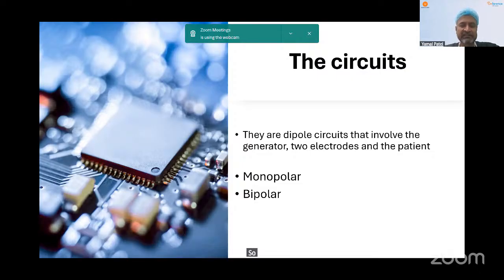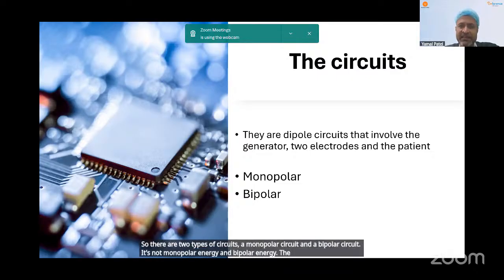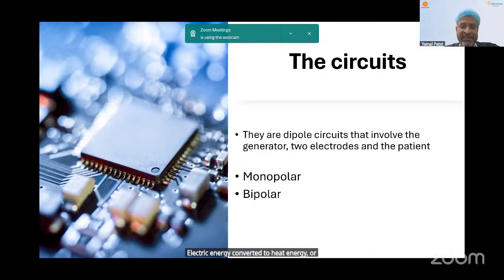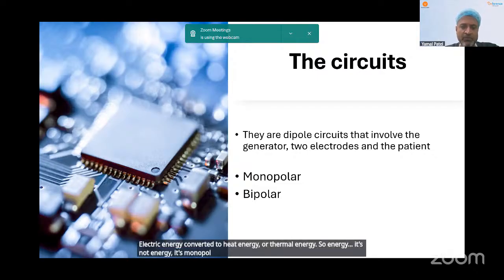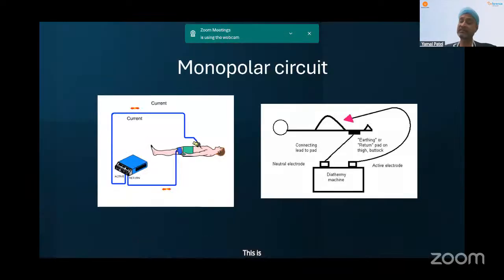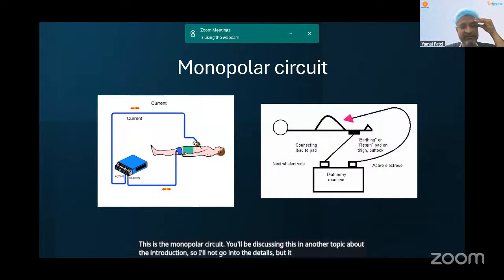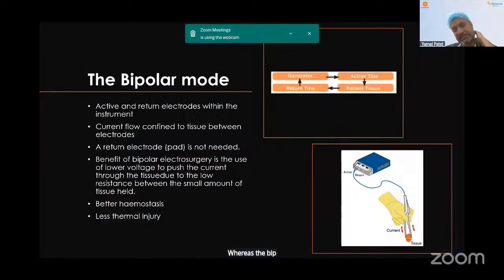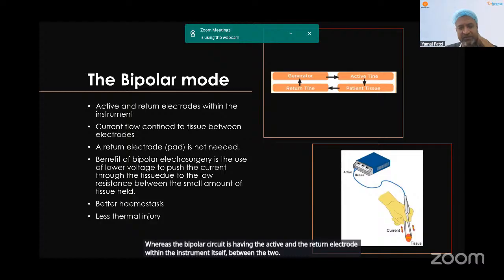So there are 2 types of circuits, a monopolar circuit and a bipolar circuit. It's not monopolar energy and bipolar energy. The energy is the same. It's electrosurgery, electric energy converted to heat or thermal energy. So it's a monopolar circuit, not monopolar energy. This is the monopolar circuit. You'll be discussing this in another topic about the introductions, so I'll not go into the details, but it requires a return dispersive electrode. Whereas the bipolar circuit has the active and the return electrode within the instrument itself, between the 2 prongs of the instrument. It therefore does not require a return or dispersive electrode.